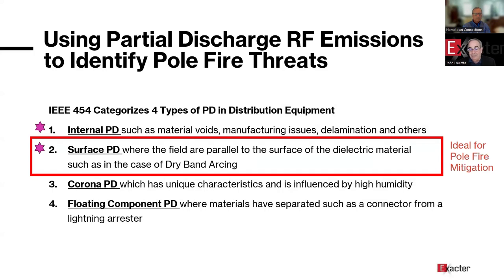And the beauty of this particular one, surface PD, is that it's a great participant in pole fires. So if you have pole fires, chances are it's surface PD, not always, but chances are that is causing the problem. And it could be something as simple as a $7 pin insulator that has dry band arcing going on. We can find it using the surface PD signatures.